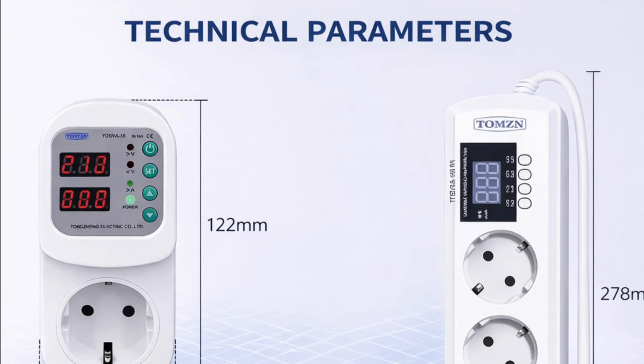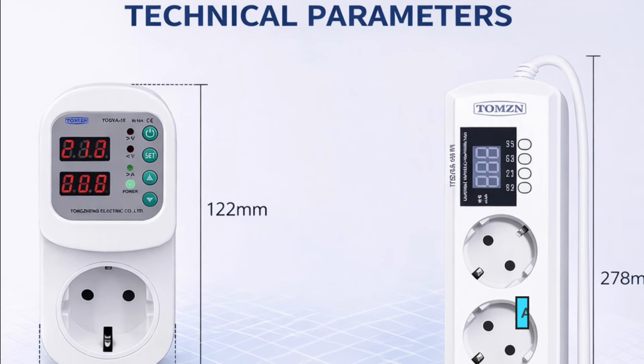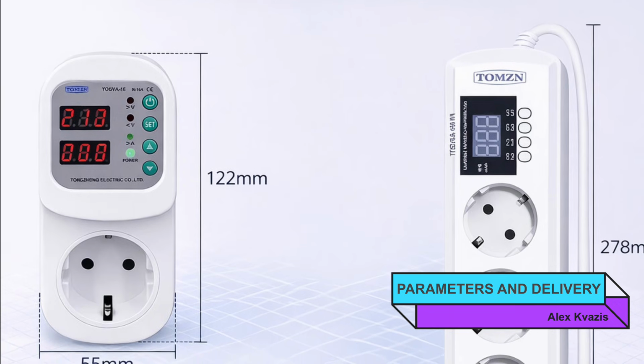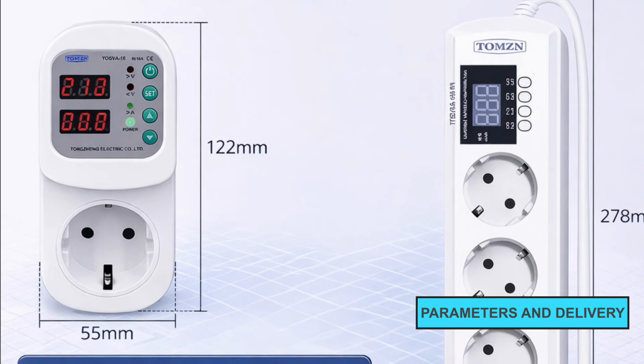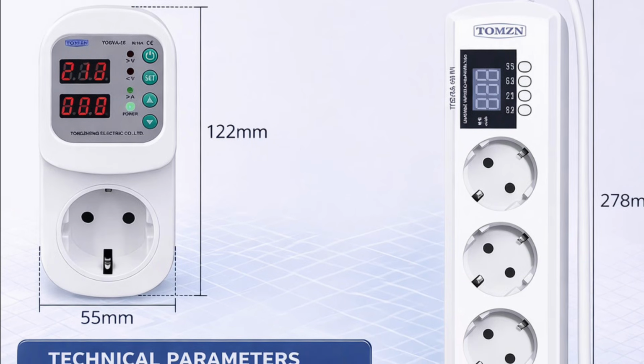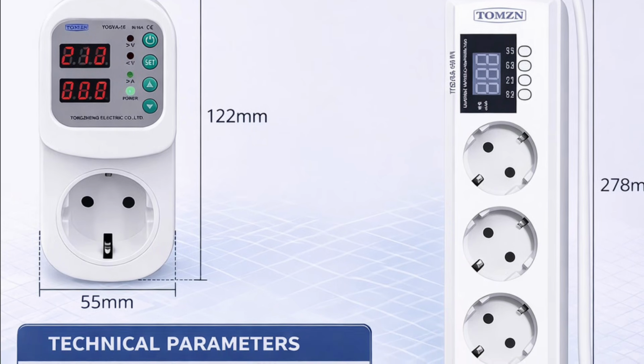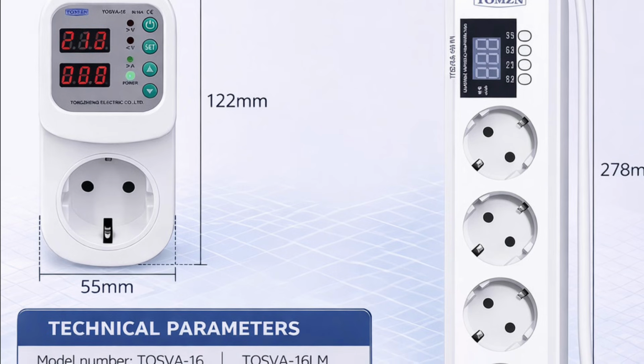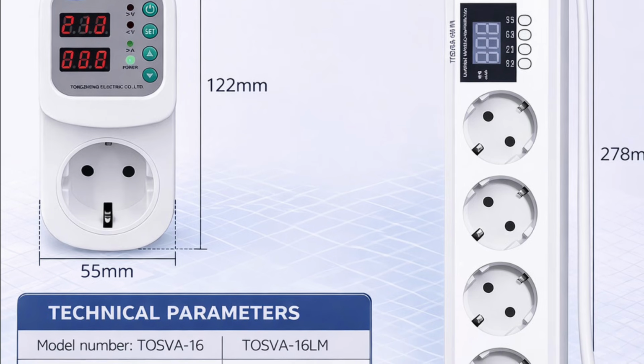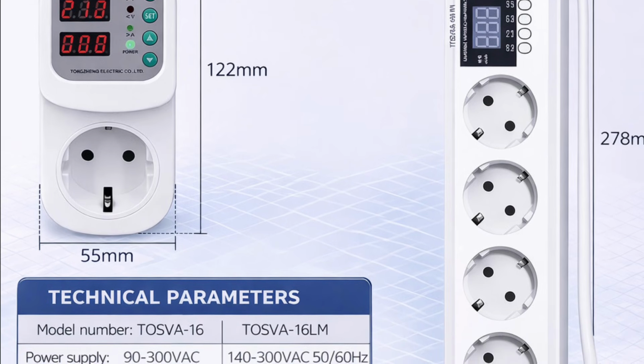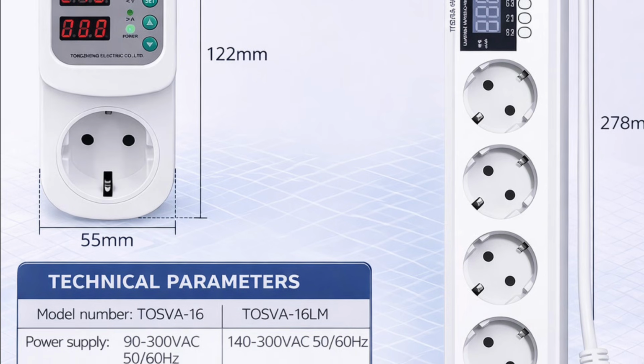Both models are voltage relays with protection against overvoltage and undervoltage, as well as overcurrent. They automatically disconnect the load in case of an emergency and turn back on by themselves after normal parameters are restored. The display shows the current voltage and current, and there is the possibility of calibrating the readings. Both devices are rated for currents up to 16 amperes, with the ability to manually adjust the shutdown threshold.